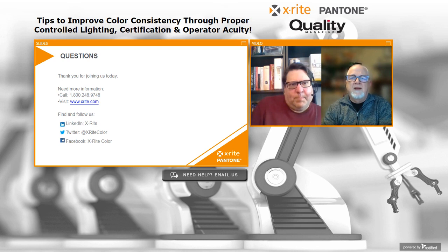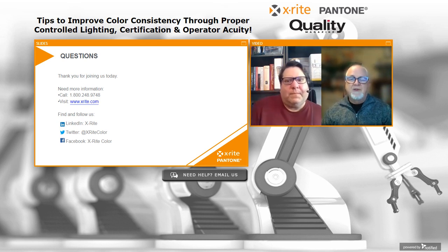They will degrade. However, an instrument, when you calibrate it, so you're calibrating it to its white calibration plaque, it's essentially calibrating the fact that the bulb is going through a change. And there are detection things in there that will detect if the light gets to a point that it no longer is emitting enough light to be calibrated. That being said, if it's 10 years old, it's probably a good idea to have that thing come in for some maintenance, right? Preventative maintenance, certification of the device, and get the light checked out.